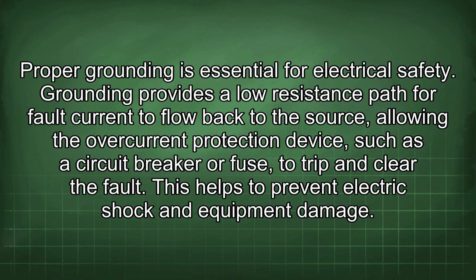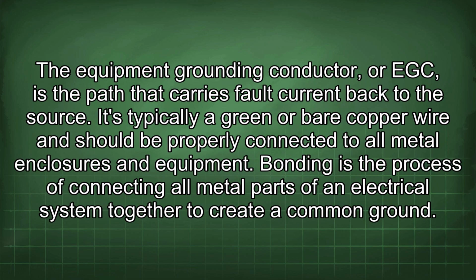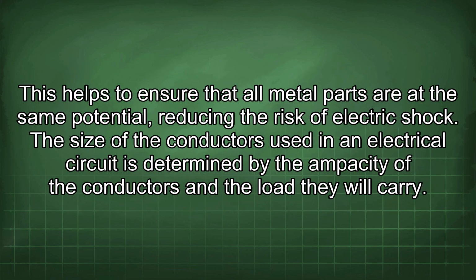Proper grounding is essential for electrical safety. Grounding provides a low-resistance path for fault current to flow back to the source, allowing the overcurrent protection device, such as a circuit breaker or fuse, to trip and clear the fault. This helps to prevent electric shock and equipment damage. The equipment grounding conductor, or EGC, is the path that carries fault current back to the source. It's typically a green or bare copper wire and should be properly connected to all metal enclosures and equipment. Bonding is the process of connecting all metal parts of an electrical system together to create a common ground. This helps to ensure that all metal parts are at the same potential, reducing the risk of electric shock.